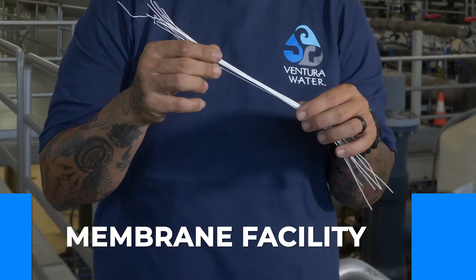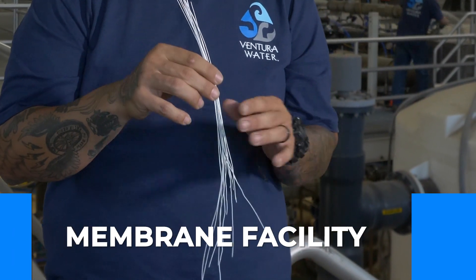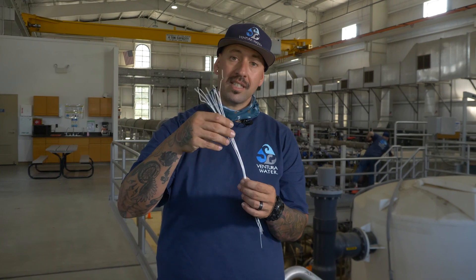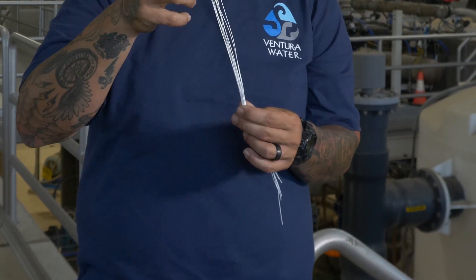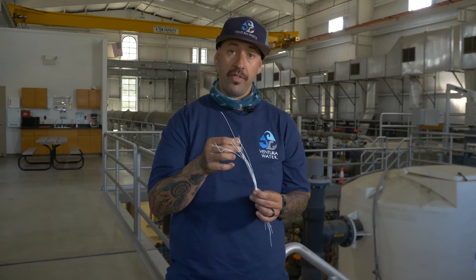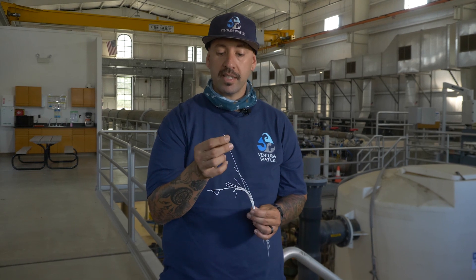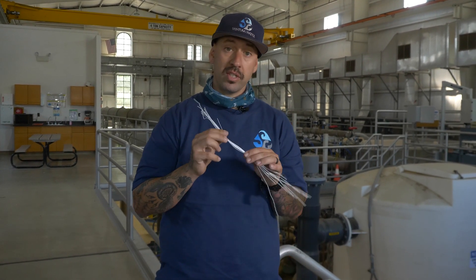We are now about to enter our membrane facility. These are the membrane fibers that are actually filtering the water — these are referenced as ZeeWeed. When these are actually in the basins, they float around in essence like seaweed, just like everybody has seen at the beach. This floats around and a vacuum is pulled on these individual fibers. It pulls water from the exterior of the membrane and processes it and flows directly through the center. That's why this is an ultra-filtration membrane plant — it has the capability of filtering out very minute microorganisms and ensures a safe drinking water product.